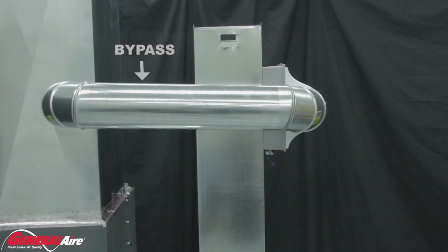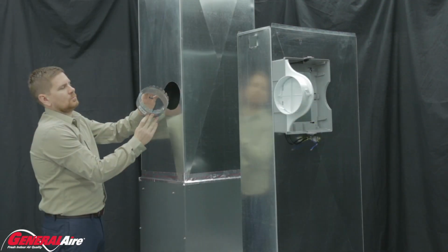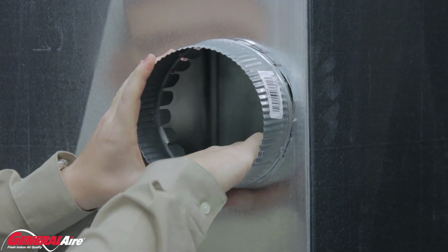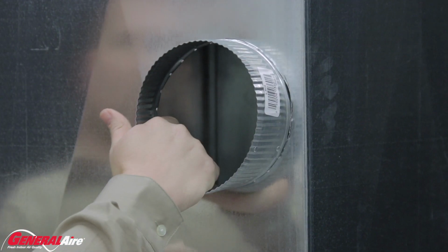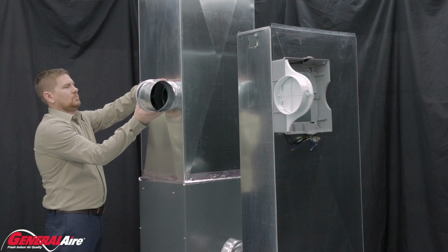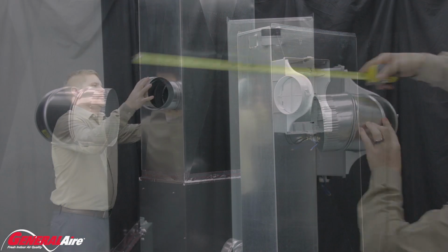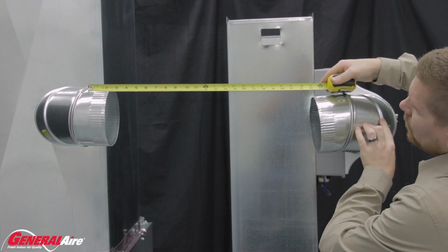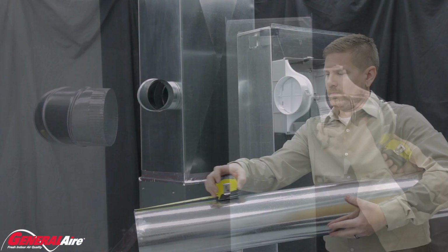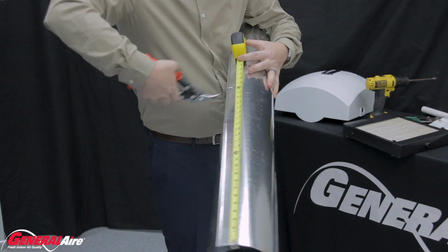Next, we will affix the bypass, which allows air to travel from one side of the ductwork to the other. Start by installing the takeoff. Work the toothed side of the A-collar into the ductwork, bending each tooth inside to secure it to the ductwork. Next, we install the pipe. The non-crimped end fits into the bypass. Measure slightly past the crimped end on both sides.